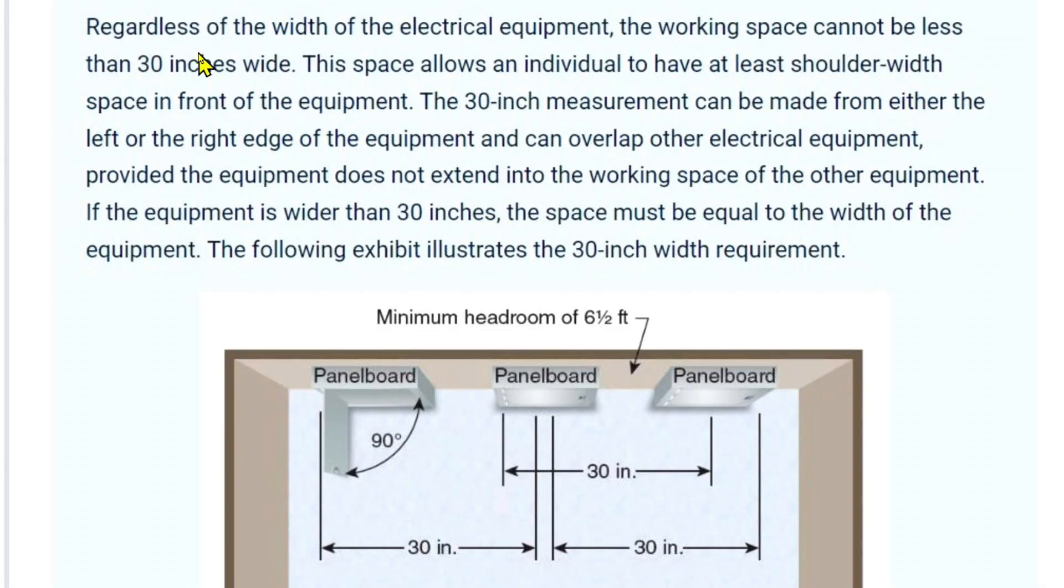This is from the 2023 NEC handbook. Regardless of the width of the electrical equipment, the working space cannot be less than 30 inches wide. This space allows an individual to have at least shoulder width space in front of the equipment. The 30 inch measurement can be made from either the left or the right edge of the equipment.